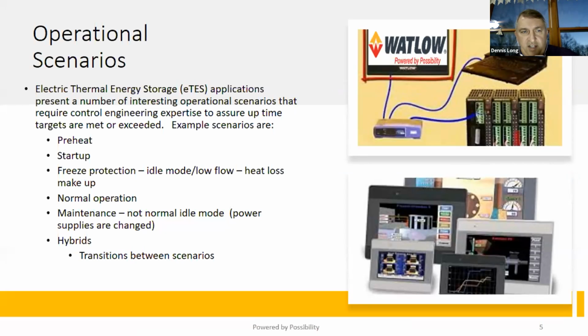Some examples of those scenarios—not an exhaustive list—include preheat, startup, freeze protection mode, also called idle mode or low flow, where normally you're making up for heat loss. Normal operation, as the system's designed to run normally. A maintenance mode, which is different from normal idle mode, where power supplies are often changed. And there could also be hybrid scenarios, with transitions between the scenarios, where the system has to be ready to deal with those changes.